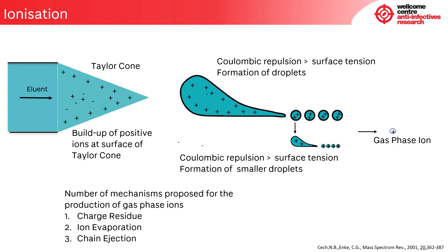If we look in more detail at the ionization process, in this case in a positive ion electrospray, there is a separation of charge caused by the voltage applied to the needle. On the Taylor cone, there's a buildup of positive ions at the surface. This leads to the emission of a stream of liquid which eventually forms a series of charged droplets. These droplets have an elongated shape, rather like a piece of chewing gum being pulled out of somebody's mouth. The buildup of charge at the surface of the droplet eventually overcomes the surface tension of the liquid, and the droplet breaks up into smaller droplets. This process can be repeated a number of times until eventually ions enter the gas phase and are then taken into the mass spectrometer.